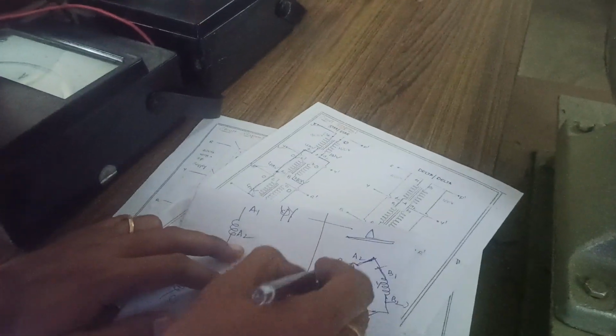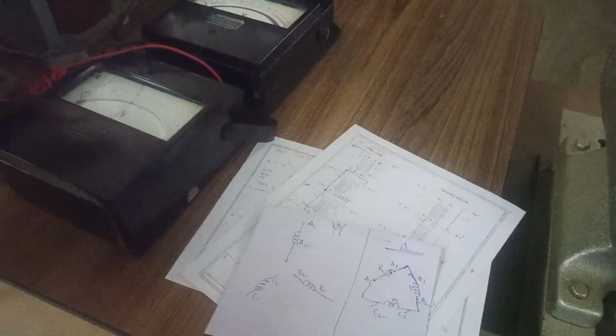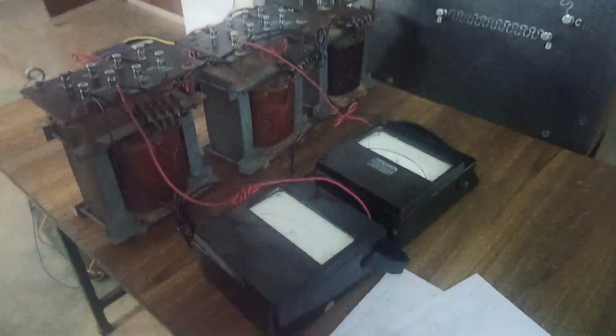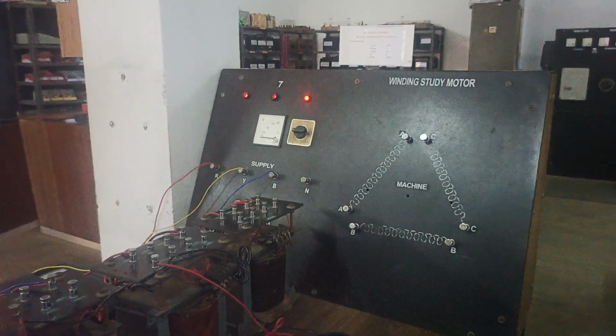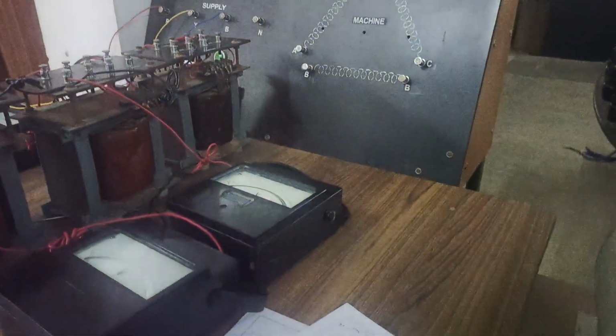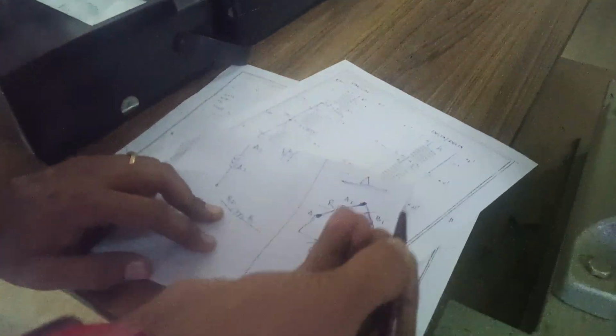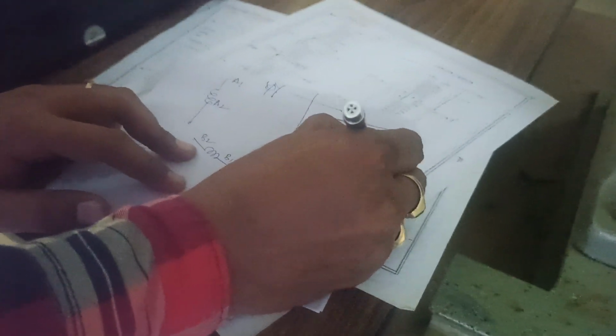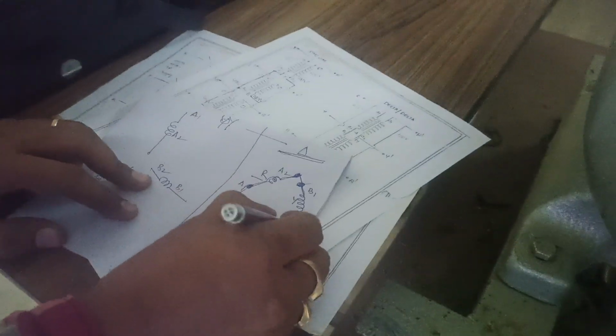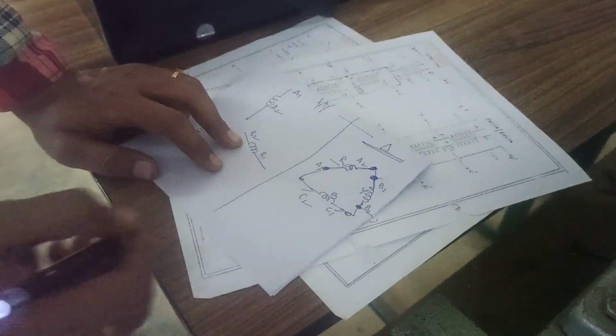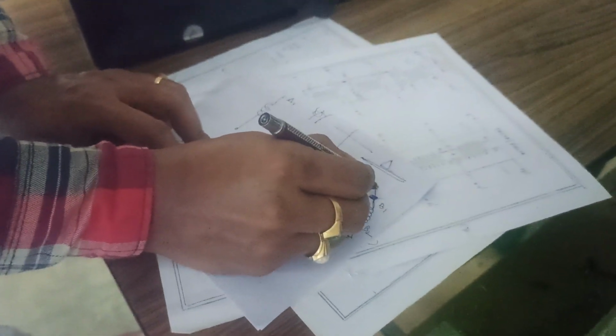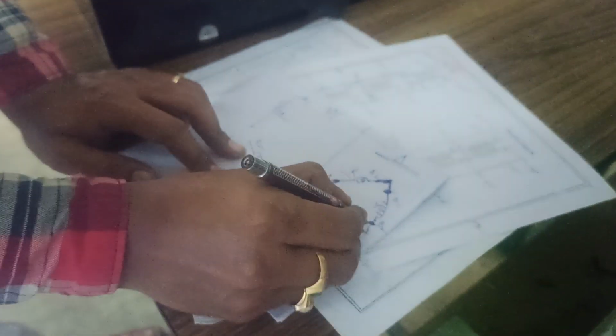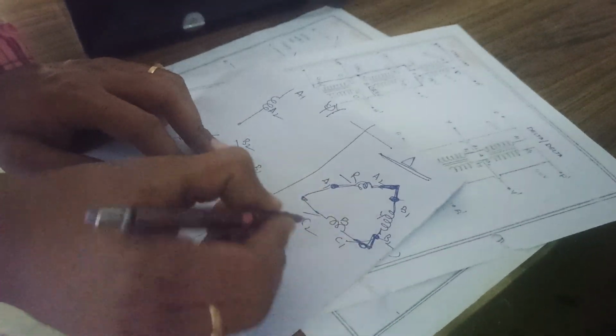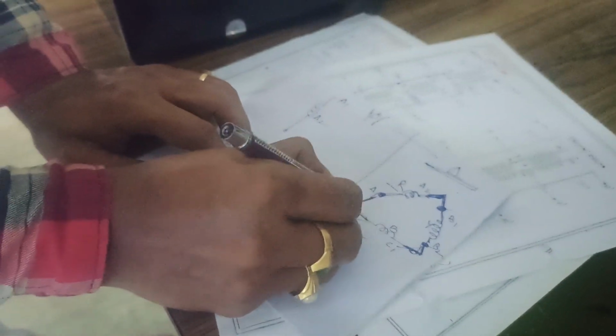So you have the R phase winding, Y phase winding and B phase winding. R phase winding has two terminals A1, A2. Y phase winding has two terminals B1, B2. B phase has C1 and C2 terminals. To connect in delta, join A2-B1 as one connection, B2-C1 as another connection, and C2-A1 as another connection.